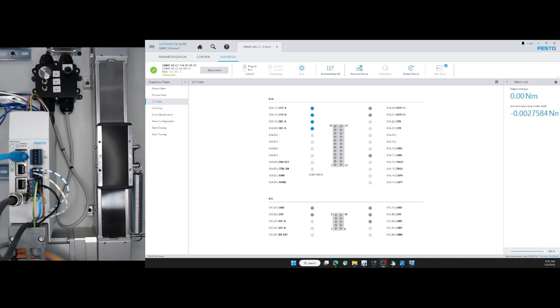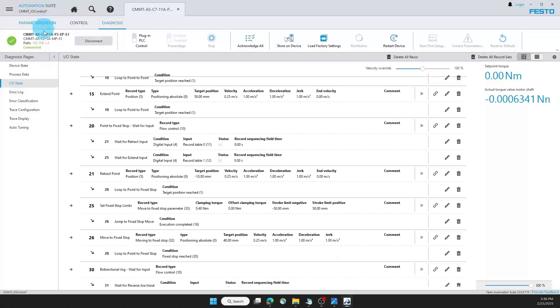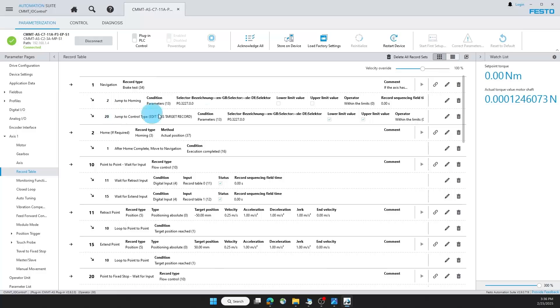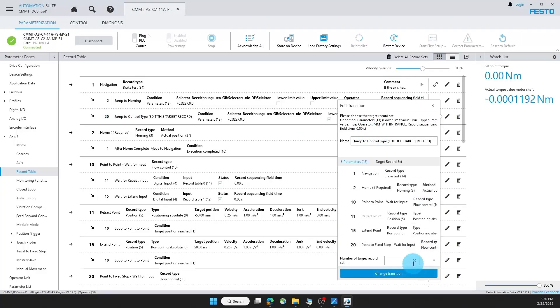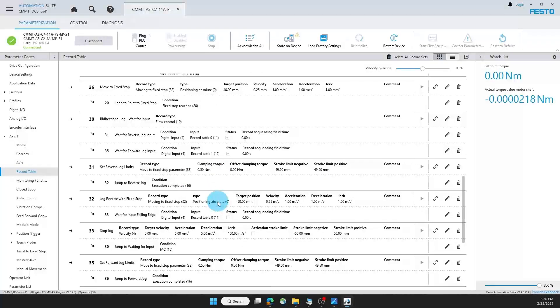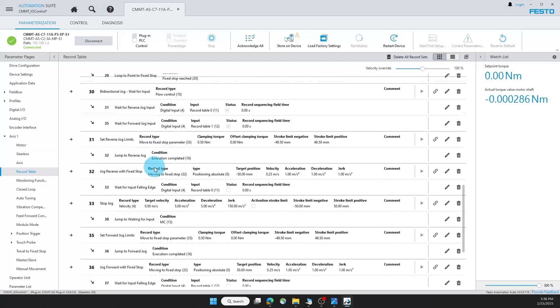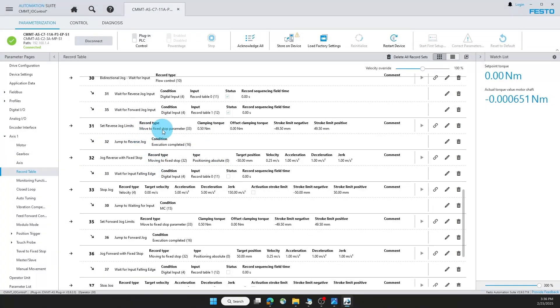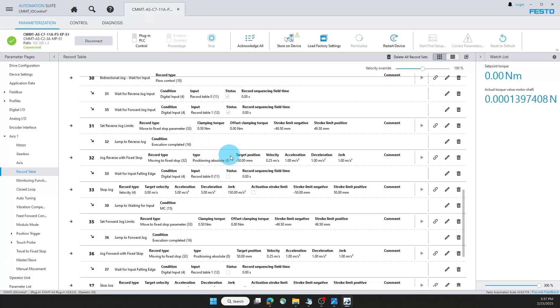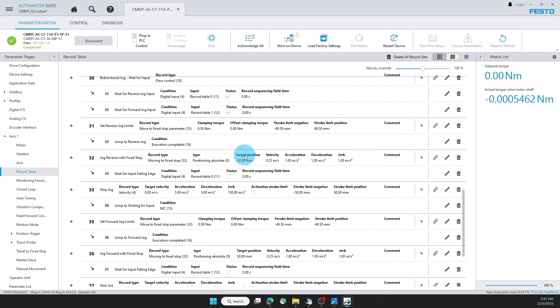Next I can demonstrate bi-directional jog. Back to the record table. I'll change this to 30. In this section I'm going to use the same fixed stop parameter and move, but for the intention of just jogging. So in this way I can find some safe limits. So what is the maximum torque I want to exert before stopping, and what's the maximum position that I want to travel to? Instead of getting an error if I held down the retract or extend bit for too long, this will define a window for the axis to move within. It will not have an error if you hold the input for too long.